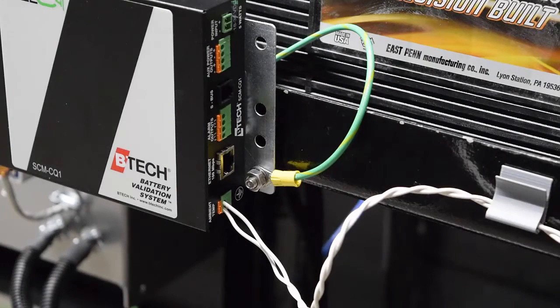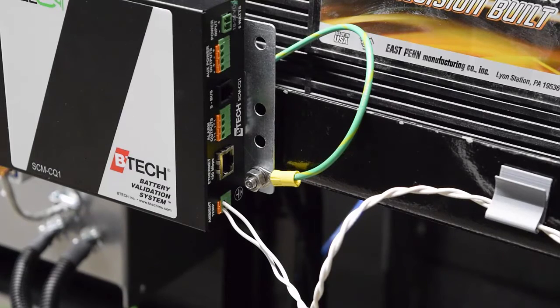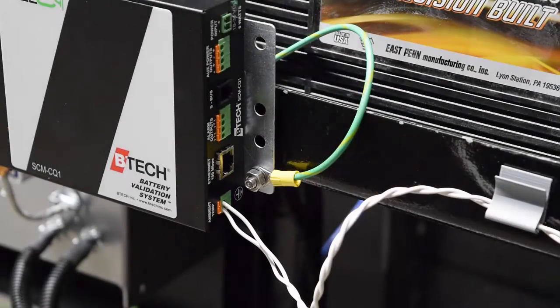It's important to ground the CellQ1 controller properly to the closest ground. In the grounding kit, there's a green grounding cable which should be connected between the CellQ1 controller and earth ground. Strip the ends of the green cable and crimp the supplied ring terminals onto it. Connect the cable between the grounding lug and a good ground. You can ground the controller to the cabinet or rack if applicable.